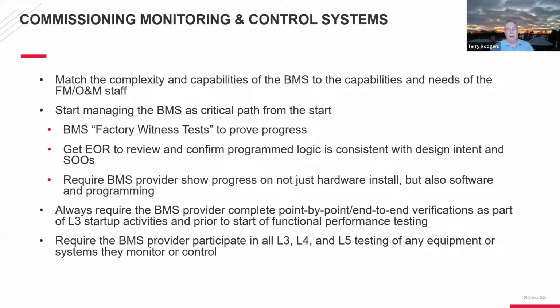One thing I highly recommend is what we call a BMS factory witness test. It's a bit of a misnomer because it's not like you're going back to the factory where the hardware is built. It's usually done at your local vendor rep's office, but he's going to have to build, configure, and put together a BAS system.